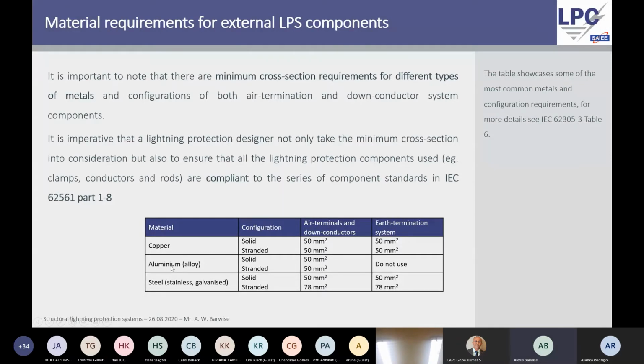If we are using aluminium as a stranded material, 50 mm squared for air terminals and down conductors, but we are not allowed to use it as an earthing system because aluminium gets corroded very quickly, and you would have to replace that earthing system very frequently.